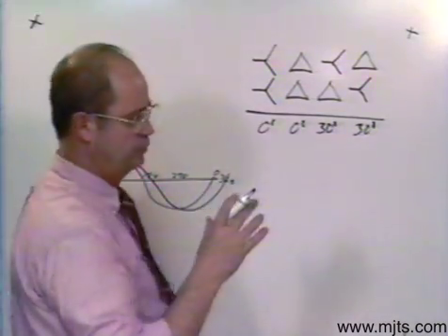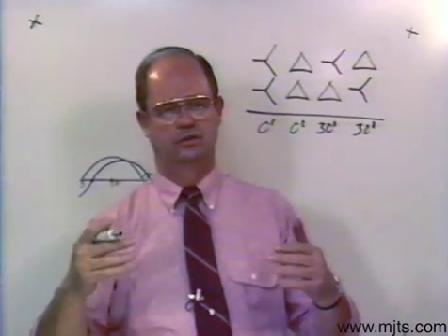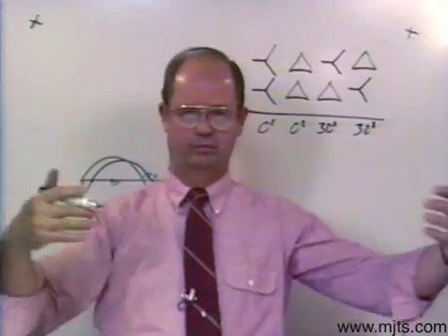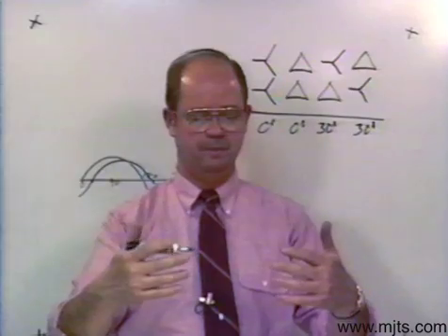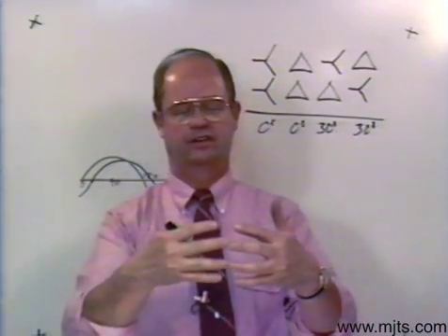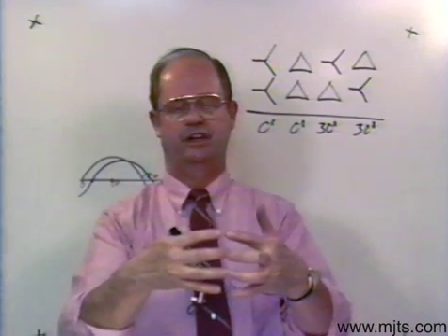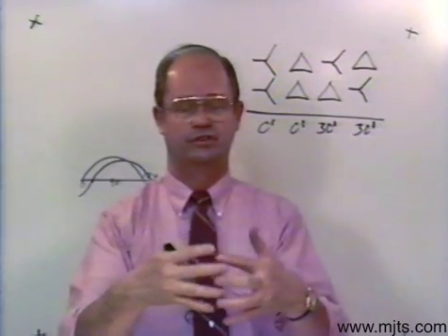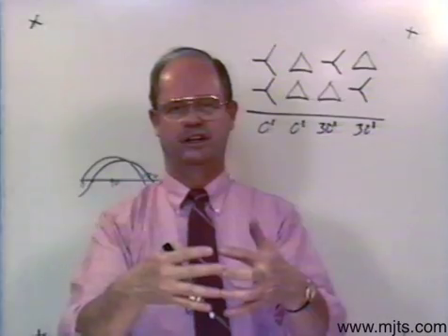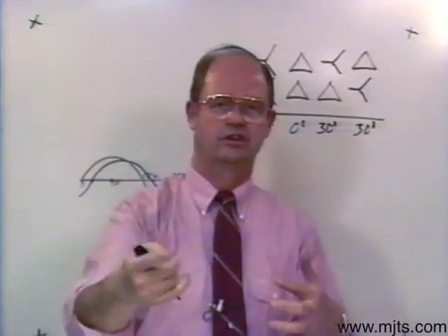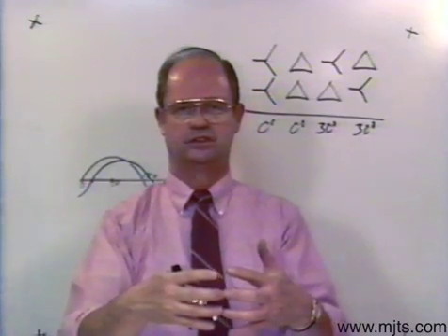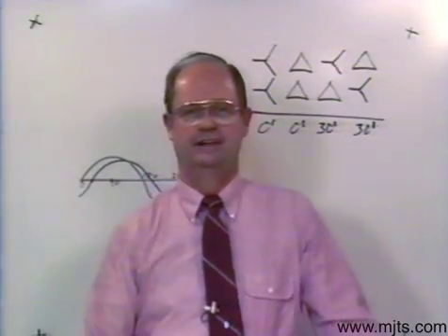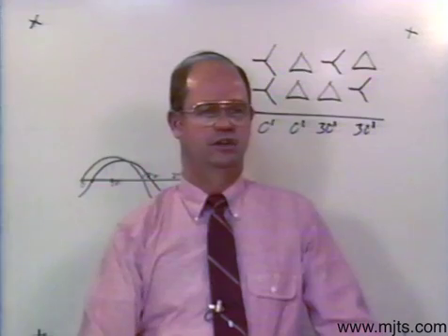Now, where this is important is when it comes into a situation where you have to tie your phases. Say I'm feeding from two different systems and I want to tie the phases together. If they aren't in the same phase displacement, then I can't tie them together because voltage-wise, there's a difference. You can't tie them together. Anytime there's a potential difference, voltage causes current to move. If I have a voltage difference between them, there's going to be current flowing, and there's a short. They have to be in the same phase displacement.